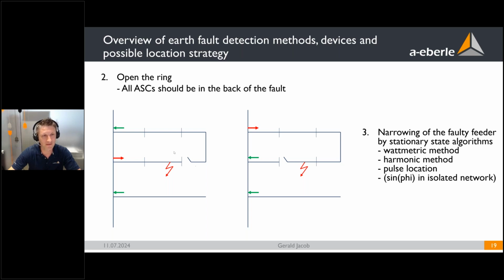So the DSO opens this switch, and the indicators change their direction. The one in the second feeder still indicates forward direction, but the first one indicates backward direction. So in the end, the DSO now knows, okay, the fault must be on these two segments in this line, and then he will switch in this breaker again, open the other one, and now he can see that the fault is not in the first segment, but in the second segment. So now he can send out his staff to really find the fault in the field, maybe only on a line which is 1 kilometer long or something like this. And as I said, the narrowing down to the faulty feeder in detail is done by these stationary state algorithms. This is not done by the QU2 or QUI method.